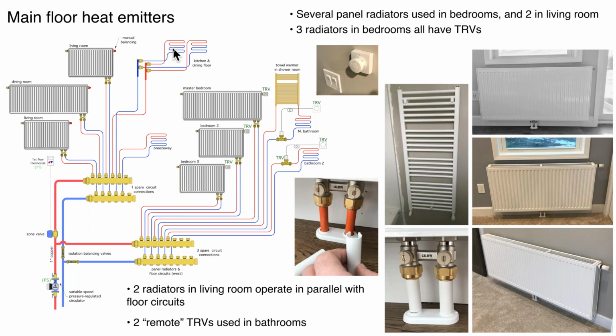And it shows you, again, a lot of flexibility here. You've got a thermostat controlling a zone valve for one area of the house. In the other areas, you've got 5 independently controlled zones using thermostatic valves. And that's all coming off of this little circulator down here. And that's the Taco circulator with the Bluetooth connection. And I can tell you, I monitored that. Oftentimes I find that running in the mid 20 watt range during a winter day to heat that entire distribution system.